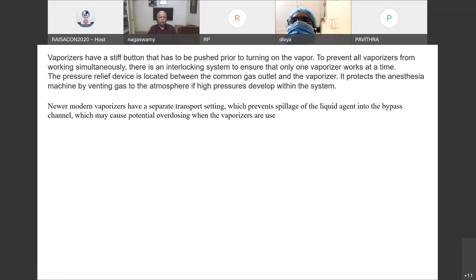And another few things: the new modern vaporizers have a separate transport setting, what is called the non-tipping setting, which will prevent spillage. It will have a mark as T, so if you turn the dial to that position T, you can even turn it upside down and nothing will spill out. And all the new vaporizers have a keyed filling or funnel filling system with unique sizing of the fillers and funnels, and also have specific bottle collars, which are filling adapters and connectors, and they have color coding also.